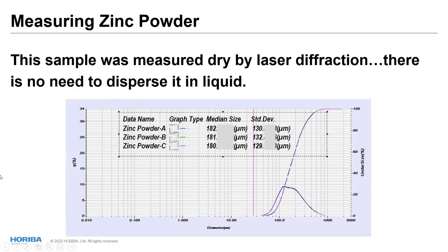Moving on in materials. This is zinc powder. We can measure it as a dry powder. And Sergey mentioned concerns about reactivity with air. If you have lithium compounds and you don't want to disperse them in water, you can run them as dry powders. But these are zinc powders, much larger materials, about 180 microns. You can see very closely grouped size results, 182, 181, 180 microns. The standard deviation listed here is due to the width of the distribution peak.